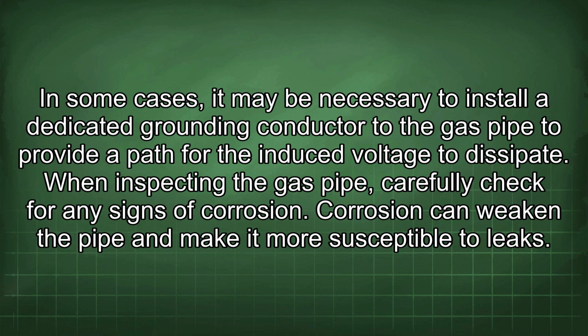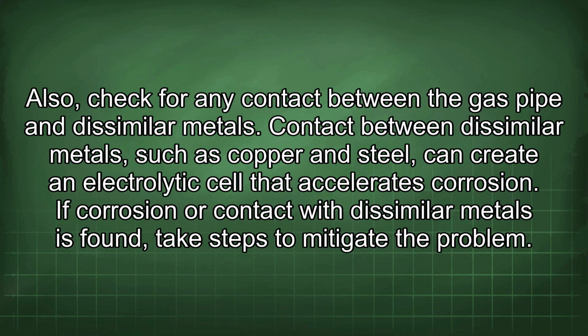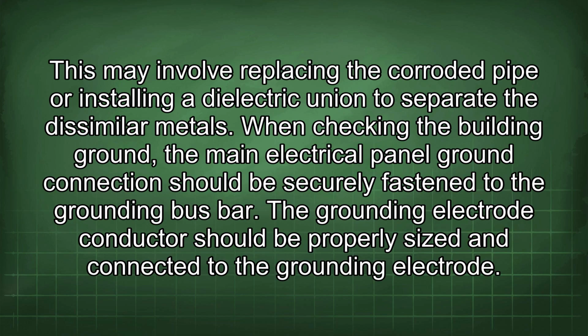When inspecting the gas pipe, carefully check for any signs of corrosion. Corrosion can weaken the pipe and make it more susceptible to leaks. Also, check for any contact between the gas pipe and dissimilar metals. Contact between dissimilar metals, such as copper and steel, can create an electrolytic cell that accelerates corrosion. If corrosion or contact with dissimilar metals is found, take steps to mitigate the problem. This may involve replacing the corroded pipe or installing a dielectric union to separate the dissimilar metals.